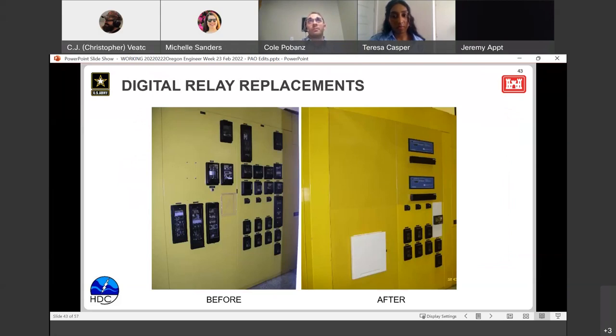The nice thing about digital relay replacements is that we originally had electromechanical relays, which are a lot bigger and a little more clunky. They worked, but we've talked about optimizing and making things modern, sleeker, and easier for the plant to maintain. Digital relays take up about half the space, and you can see that in this giant yellow cabinet here. The electromechanical relays take up the entire thing with tons of weight and floor space, but on the right you can see we've gotten rid of half the cabinet. This is all empty space here on the left, and it's just full of digital relays that take up a lot smaller amount of space.